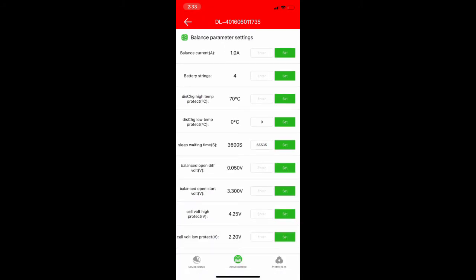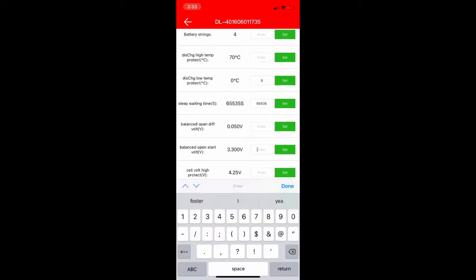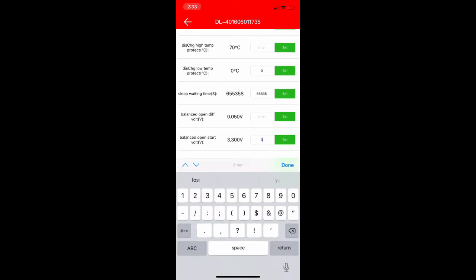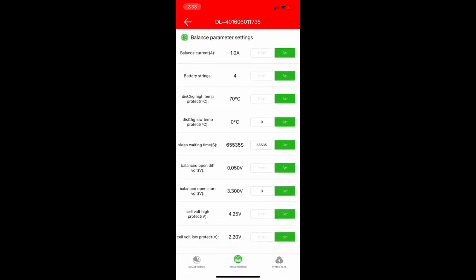So we'll hit set. The balance open diff is currently 0.05 volts, which I believe is fine to leave. The balance open start is currently set to 3.3 - I would probably change this down to 3 volts, if not a little lower, which is just what voltage you want it to start balancing at. So I'll change this to 3 and hit set.